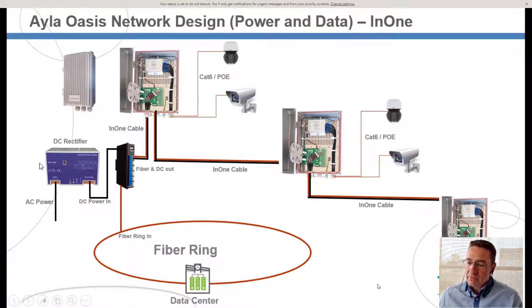As you see, AC power is needed only in one or several locations — I'll discuss this more in the design. After that, you only need to pull the fiber cable that also carries the power needed to feed all the cabinets. No need for any AC-to-DC rectifier at each site, no UPS, no ventilation, no AC power source — just the hybrid fiber and power cable, the InOne cable, all the way from one cabinet to the next.